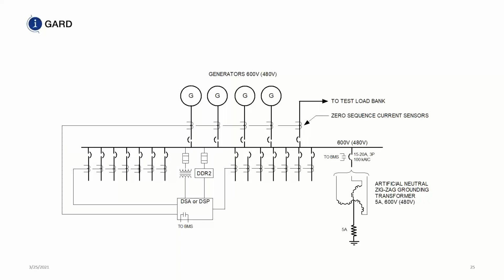If you put a high resistance grounded system on each one of the generators, in this particular example, if you have 4 generators on a 600 volt system or 480, if you put a 5 amp resistor on each generator, if all 4 generators are running, you're going to have a maximum fault current of 20 amps. What happens if you have a fault current of 20 amps is you don't get the benefit of staying online if there's a fault on the system. You don't get the benefit of having an arc flash mitigation technique.